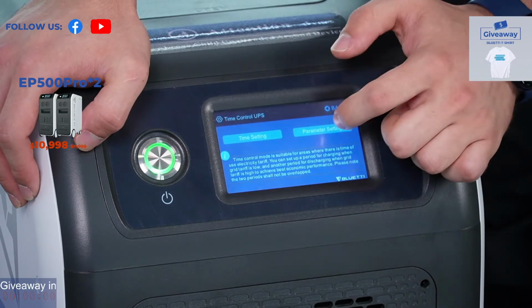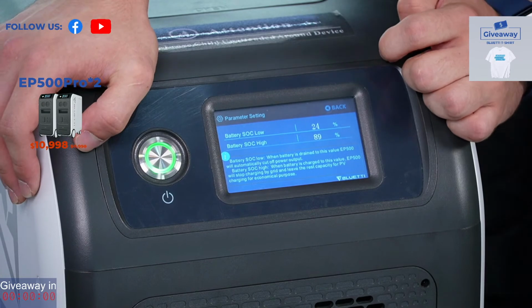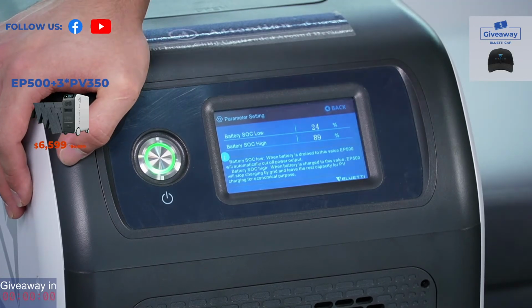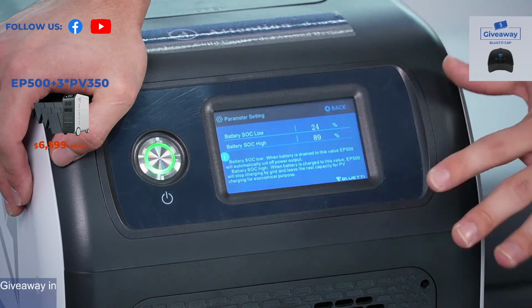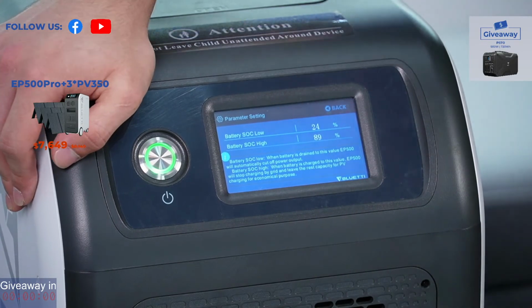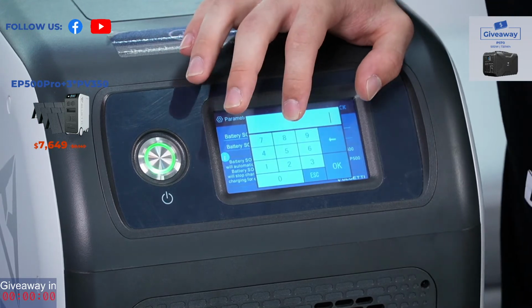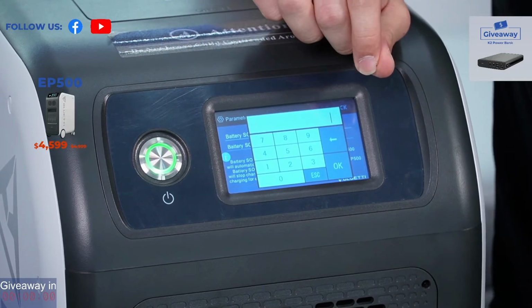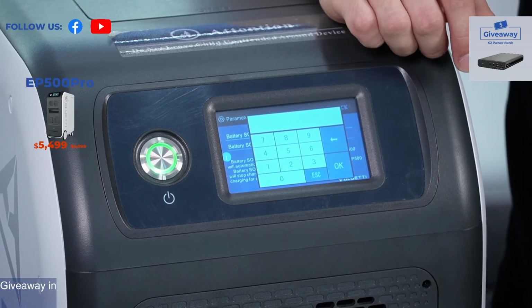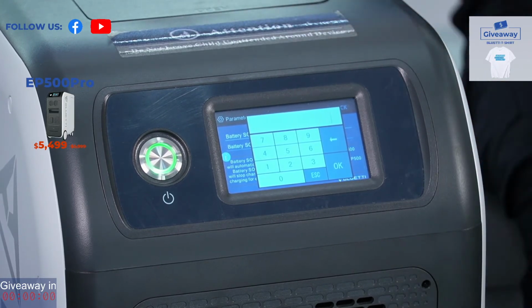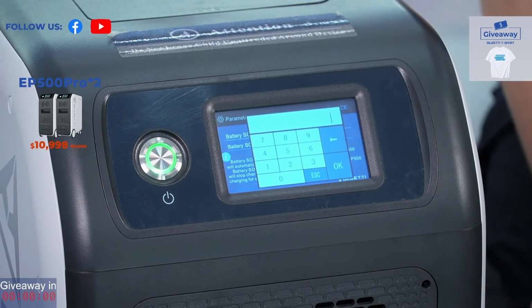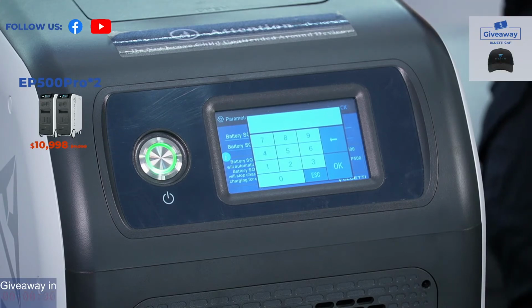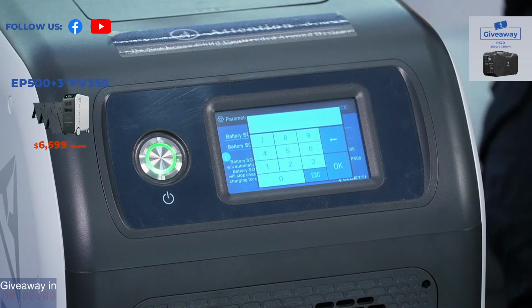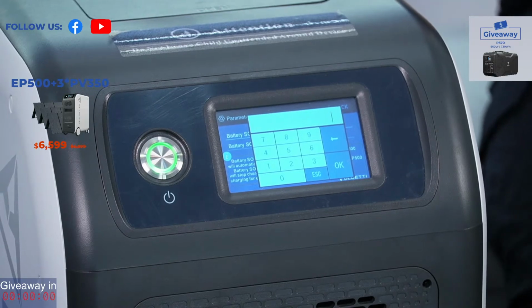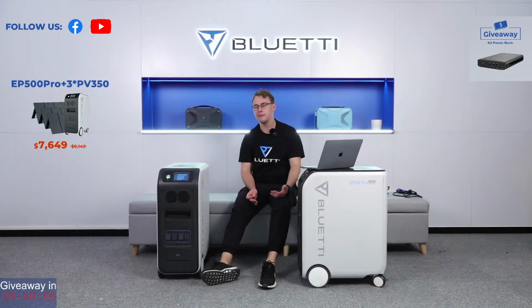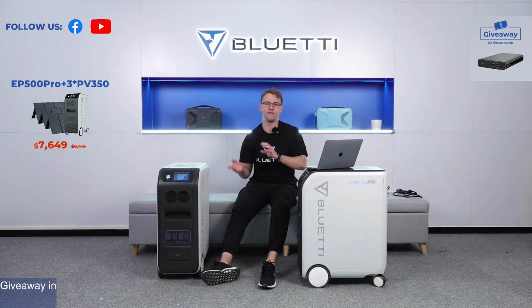Let's go back to parameter settings. This is battery SOC, state of charge, low and high in this order. First you want to set the SOC low. Specifically, you don't want to always go all the way down to 0%. Of course nobody wants to do that. Even with our phones, we don't always drain them to 0%, hopefully. We know it damages the battery, especially long-term. So we don't want to go all the way to 0%, but how low do we want to go? Maybe 5%, maybe 10%? I'd say the sweet spot is around 15-20%.